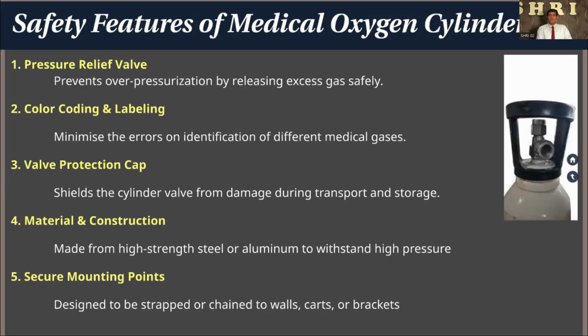You can see the domestic LP gas cylinder that carries the valve cap, which is fixed to the cylinder. But what happens when cylinders come to our hospital? The people handling the oxygen cylinders remove this valve cap because it is quite practically difficult to connect the oxygen regulators with this cap. To make their life easy, they remove the cap, but leave the nozzle exposed to the environment. So always, if you have the cylinders, if possible, keep the valve cap. That is a very good safety measure.